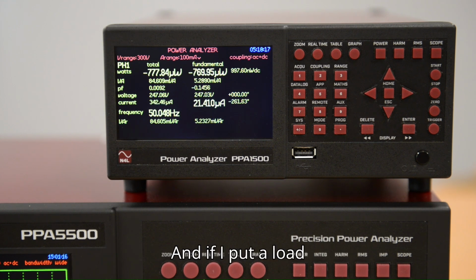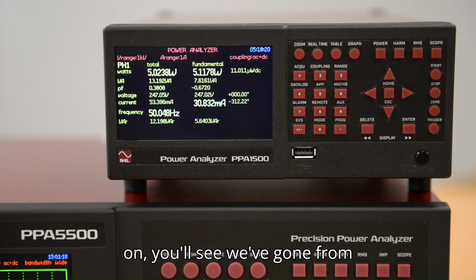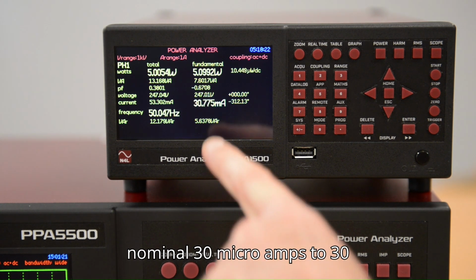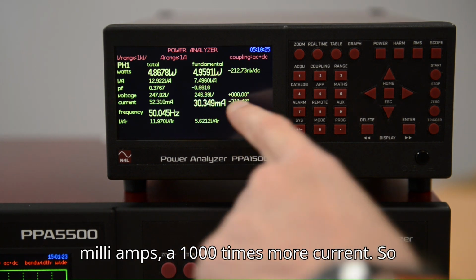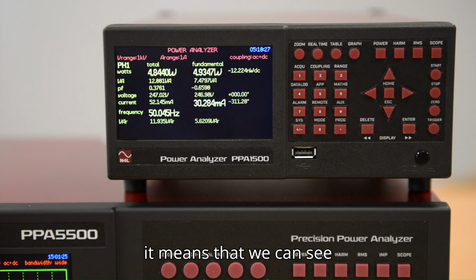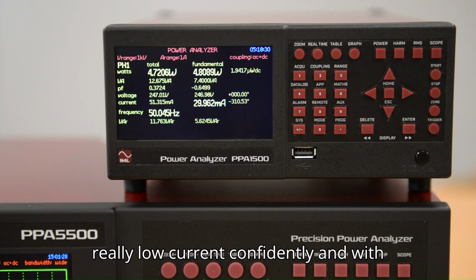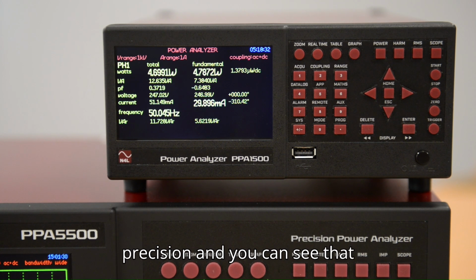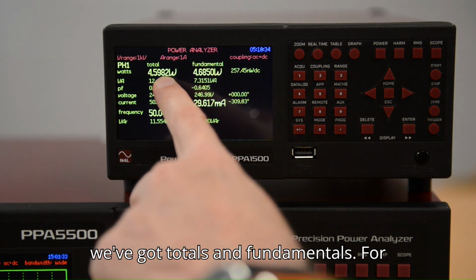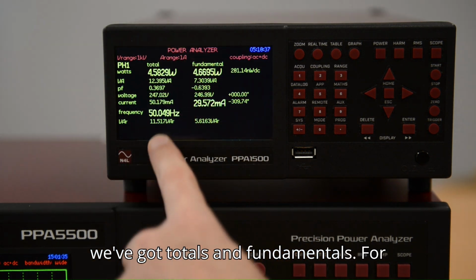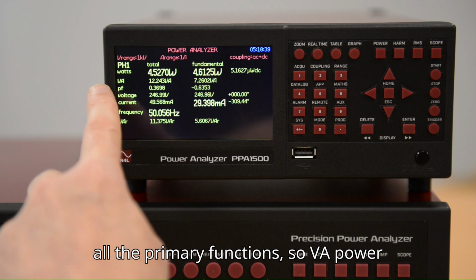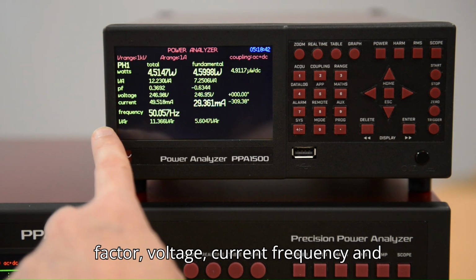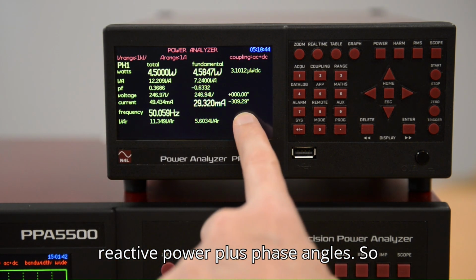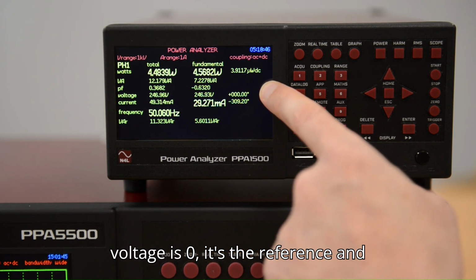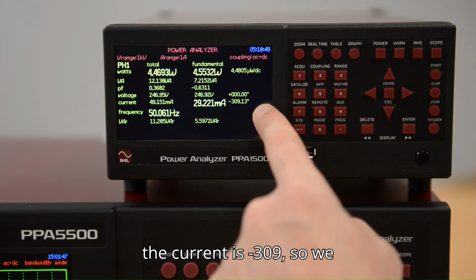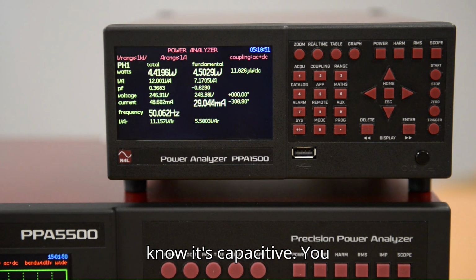And if I put a load on, you'll see we've gone from nominal 30 microamps to 30 milliamps, 1,000 times more current. So it means that we can see really low current confidently and with precision. And you can see that we've got totals and fundamentals for all the primary functions, so VA, power factor, voltage, current, frequency, and reactive power, plus phase angles. So voltage is 0, it's the reference, and the current is minus 309, so we know it's capacitive.